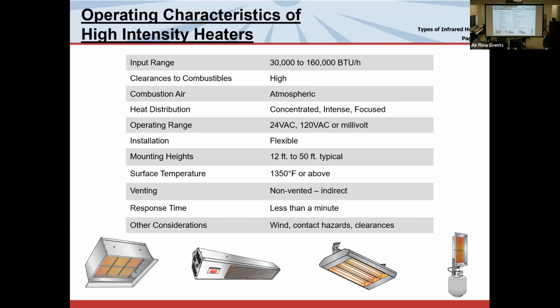Problem with these ceramic heaters, okay? This particular patio and this particular DR series heater, you cannot direct vent the heater. There's no way to get the products of combustion out directly. So you have to introduce ventilation into the building, okay? This is also true for tube heaters. People think you have to vent a tube heater. You don't. You just have to provide 4 CFM per 1,000 BTU. And that is an answer, you know, to a lot of complicated problems.